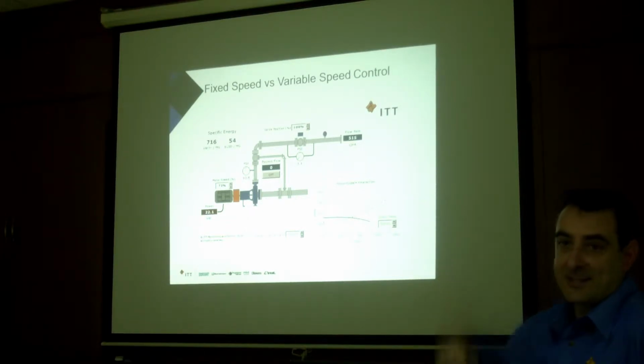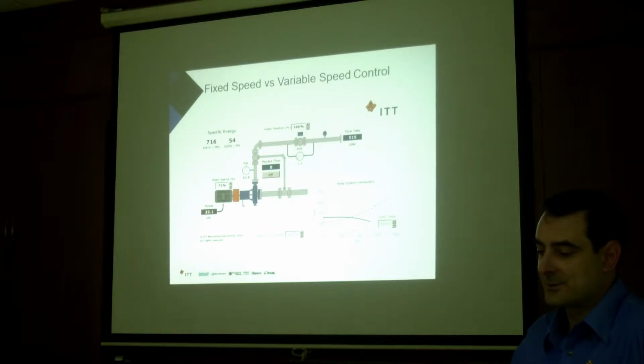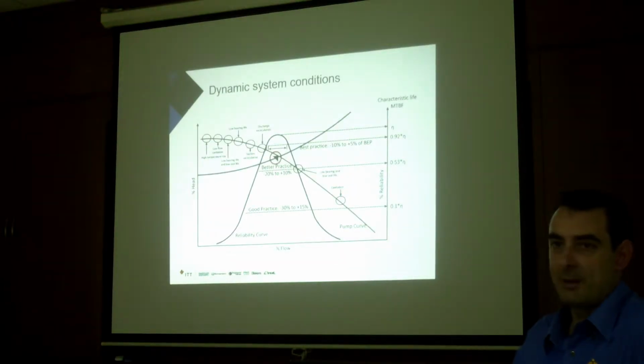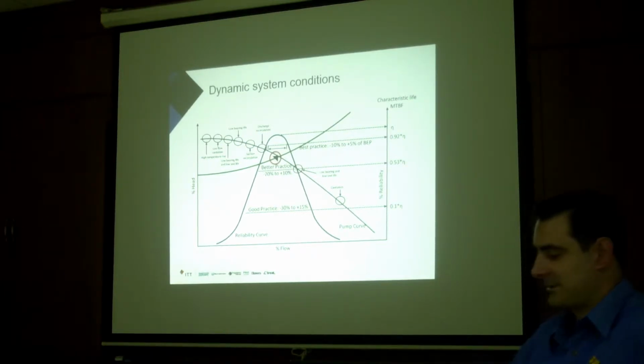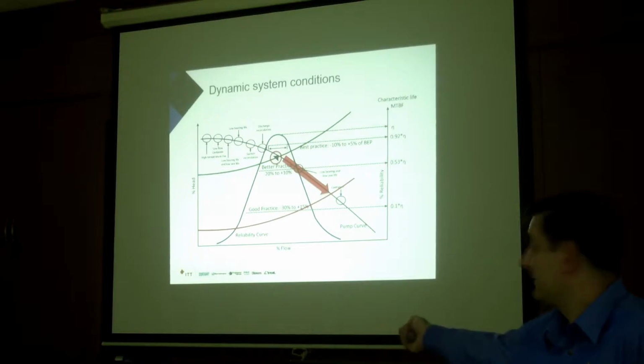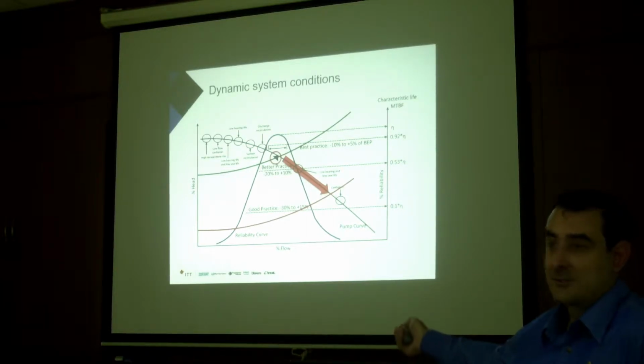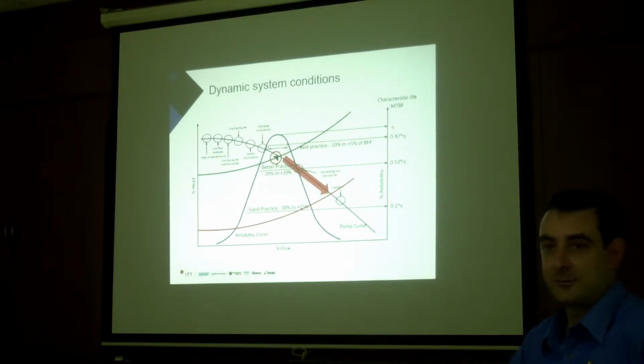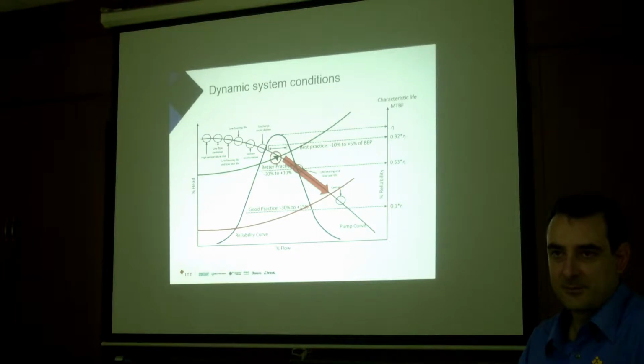So again, at that tank terminal where they're using Danfoss, they're not concerned about where the pump is. They start lowering the speed when the tank level goes down, but it just makes this condition even worse. So they are so far off the end of the curve that the curve doesn't exist. So they get cavitation. But they blame the suction pressure. But really that's the run-out condition.